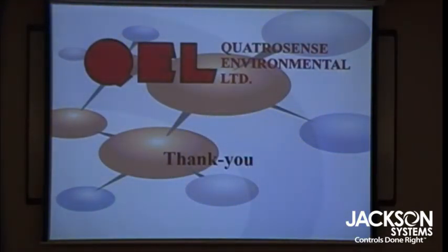Yeah, so the sensor lifetimes are good, at least 5 years for CO sensors. The NO2 sensors 2 to 3 years. Replacement cost is very reasonable. Our after-sale service is excellent. If you need to talk to a technician to program a unit, or you have something wrong with the unit, call us. We will tell you what to look at on the board, or read the error codes, and we'll tell you, okay, you've got to send it back to the factory, or no, reset it, or just move this over, and you can get it up and running. So it's our technical support, as you say. You guys do a very good job.